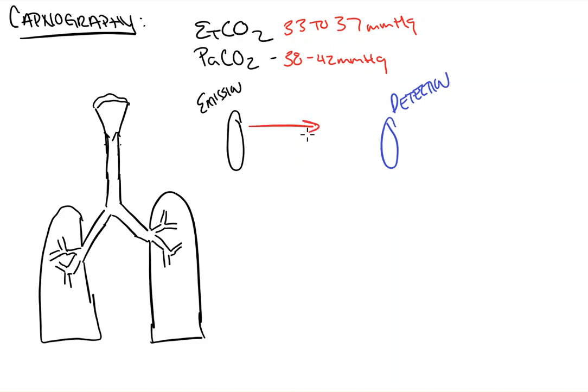Infrared light is sent across at 4.25 micrometers. And this is the same wavelength that interacts with and is absorbed by our CO2 molecules. So as a gas sample enters the monitor, various amounts of light from the emission source will reach the detection point, based off of the amount of CO2 inside.